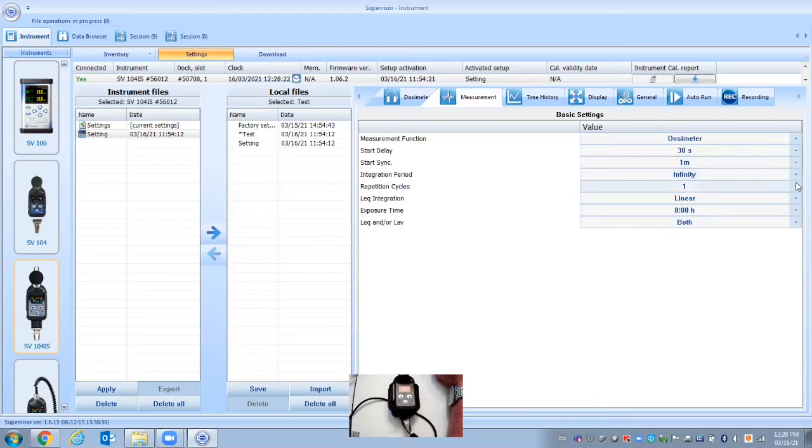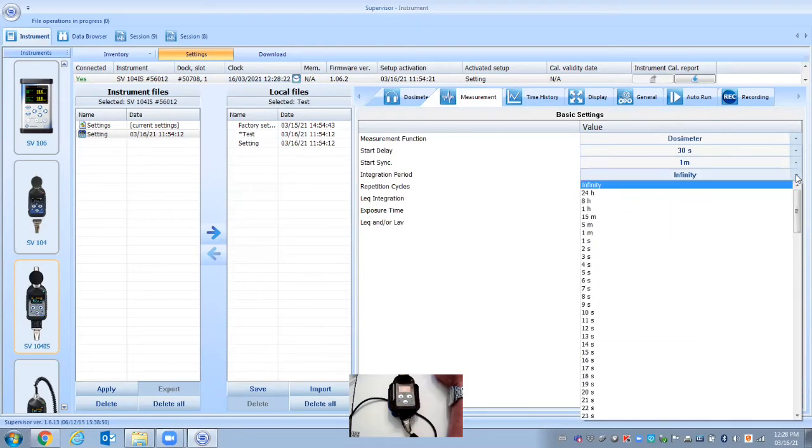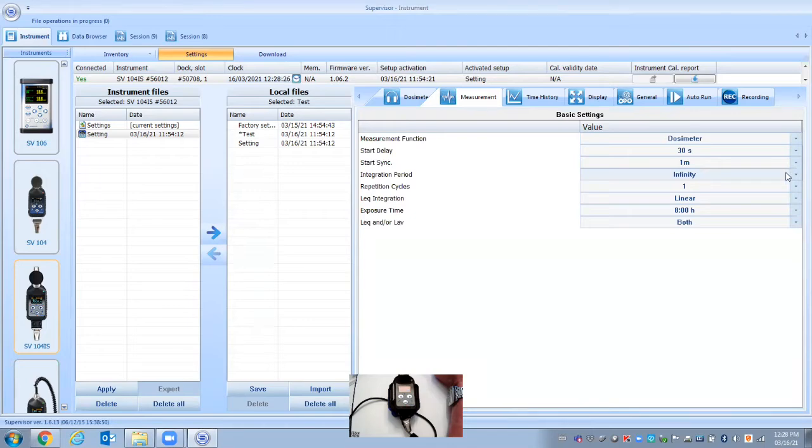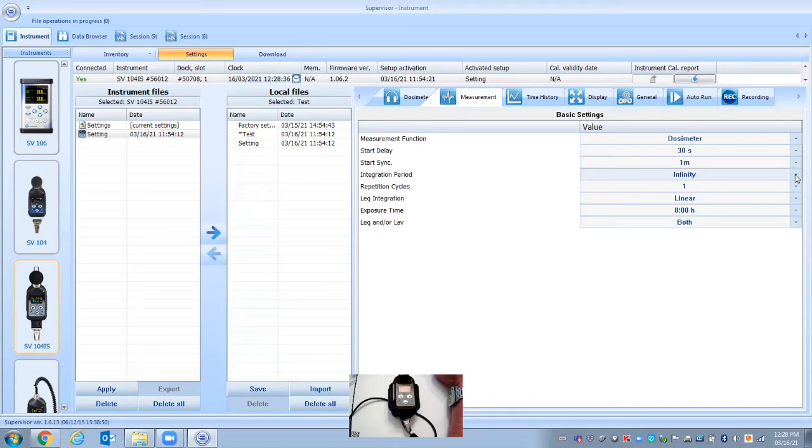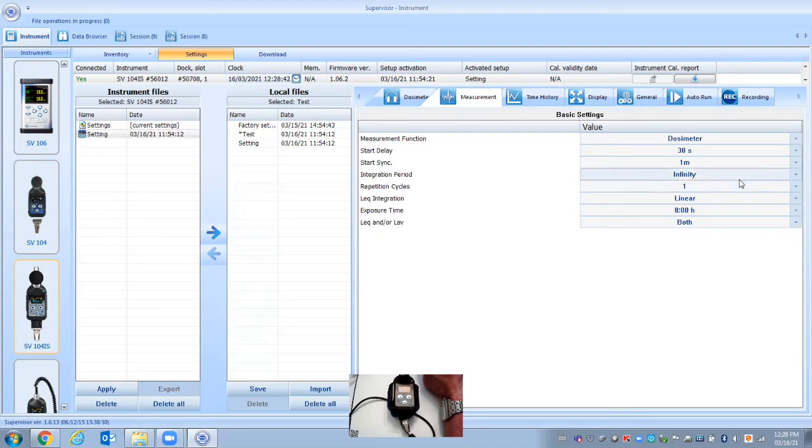We can either have it, well, if you're doing a basic setup, probably the best thing is just to have it as infinity. So when you hit start on the dosimeter, it'll start to record and it will stop when you take it off the person and hit stop.